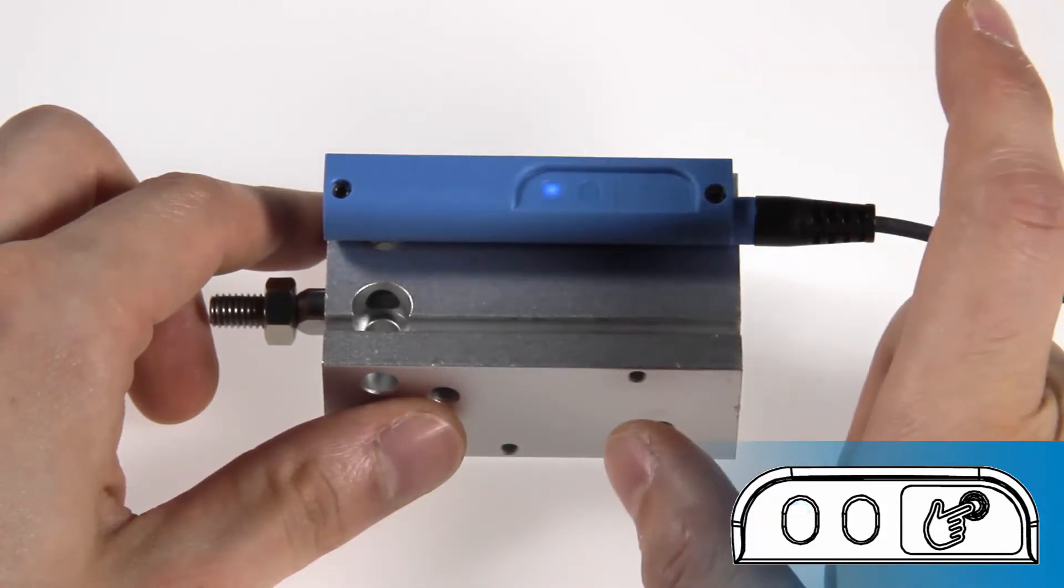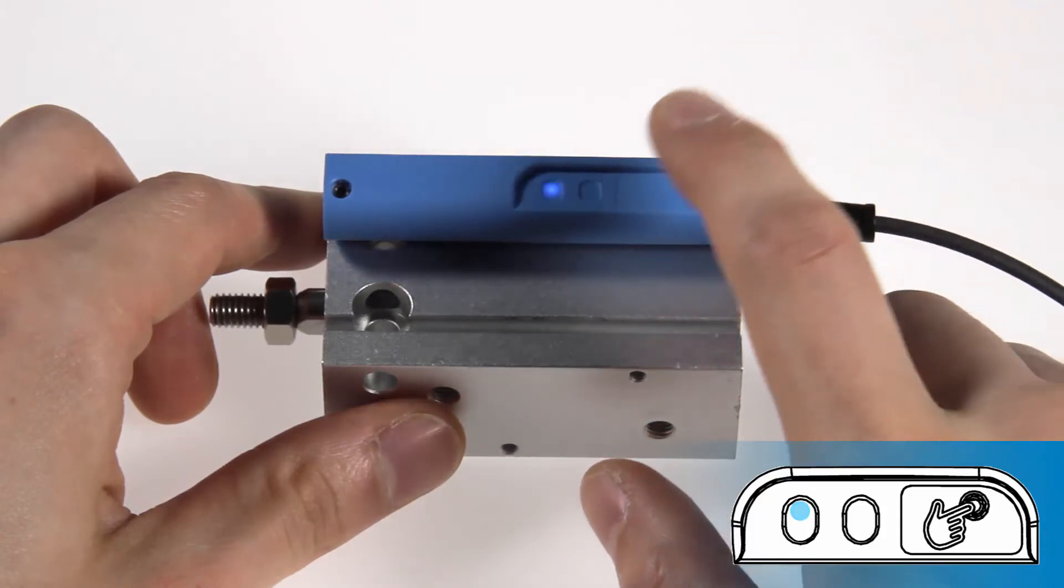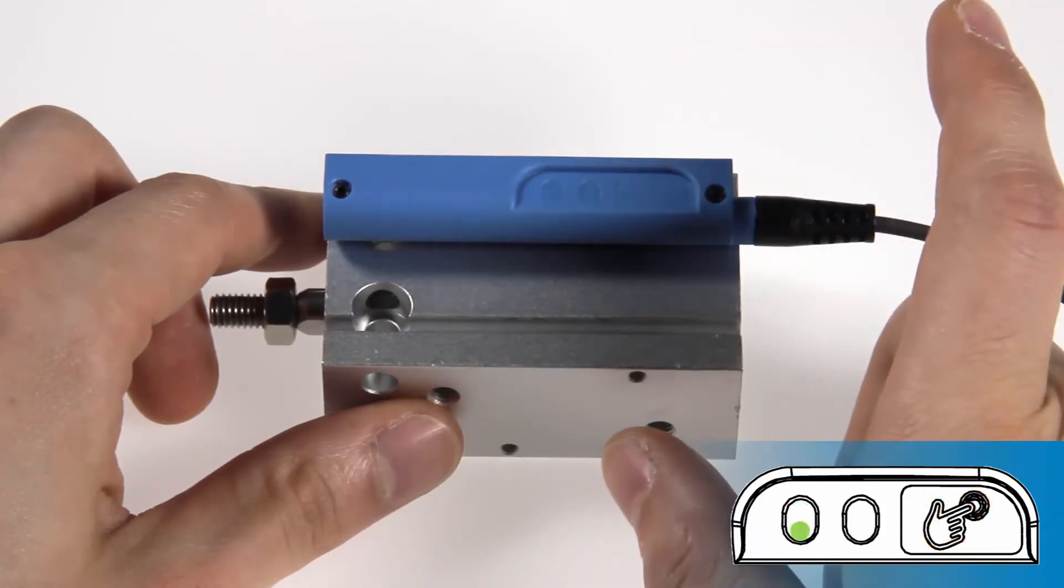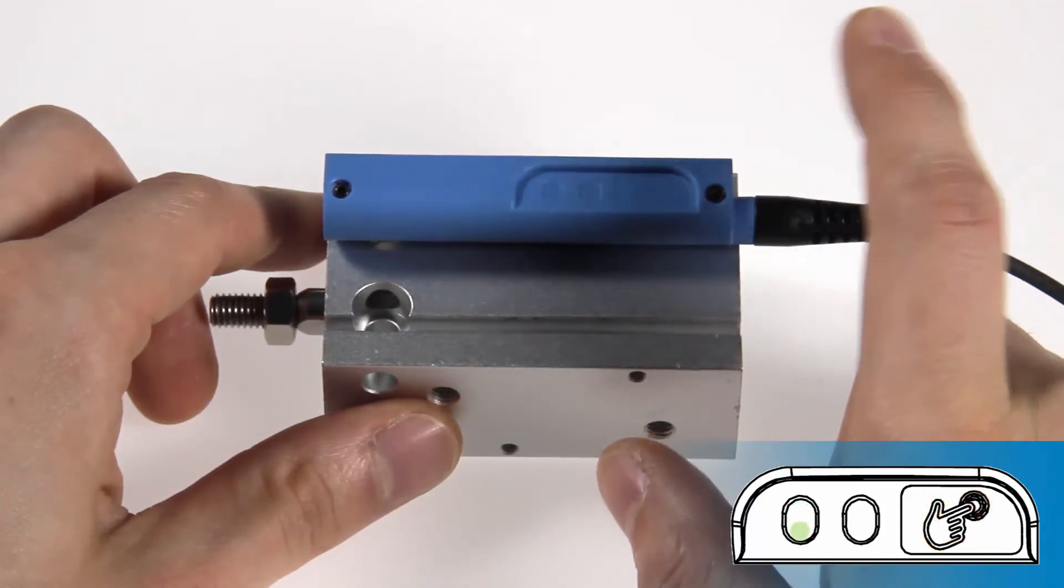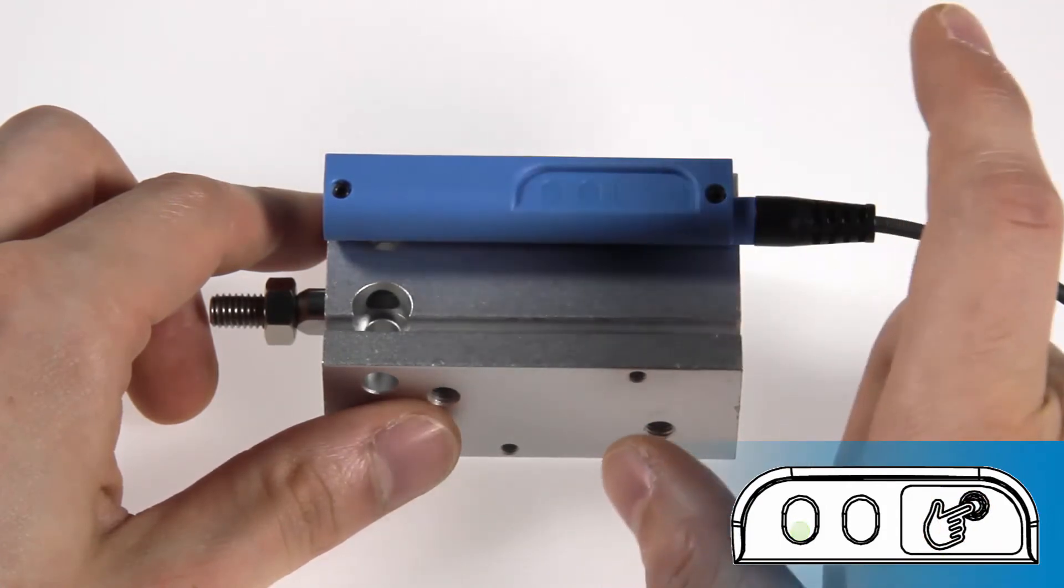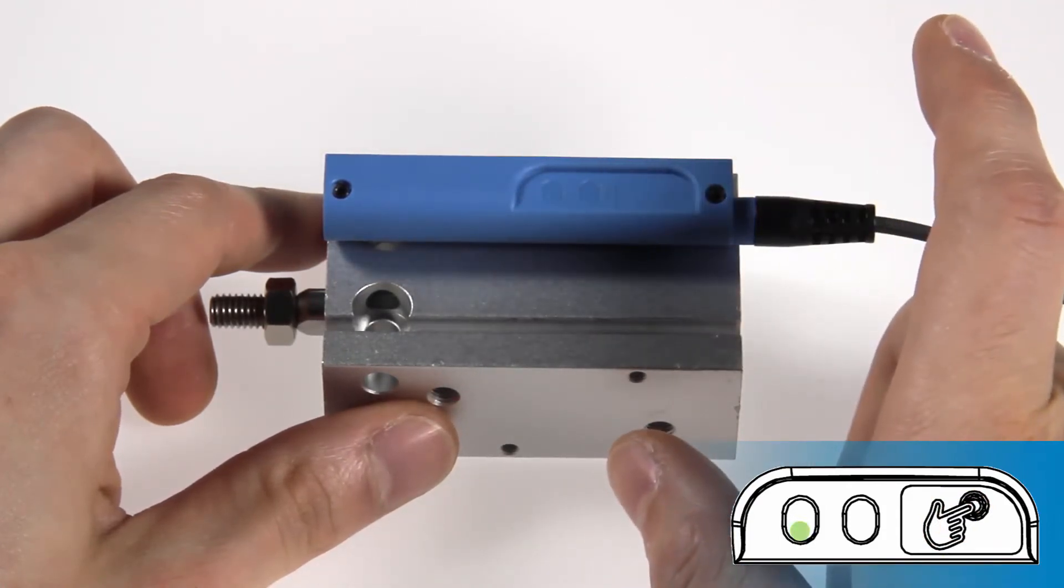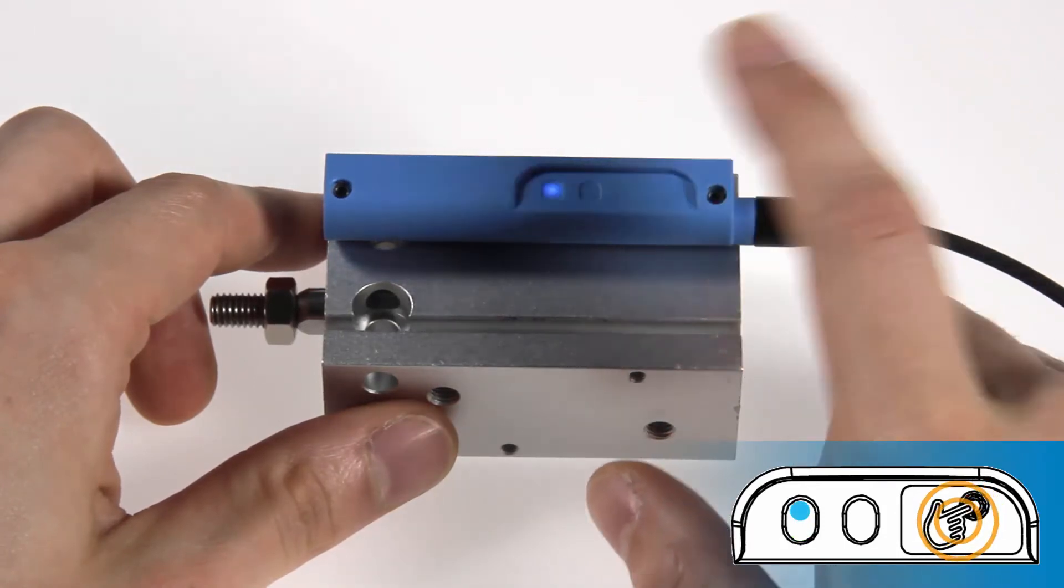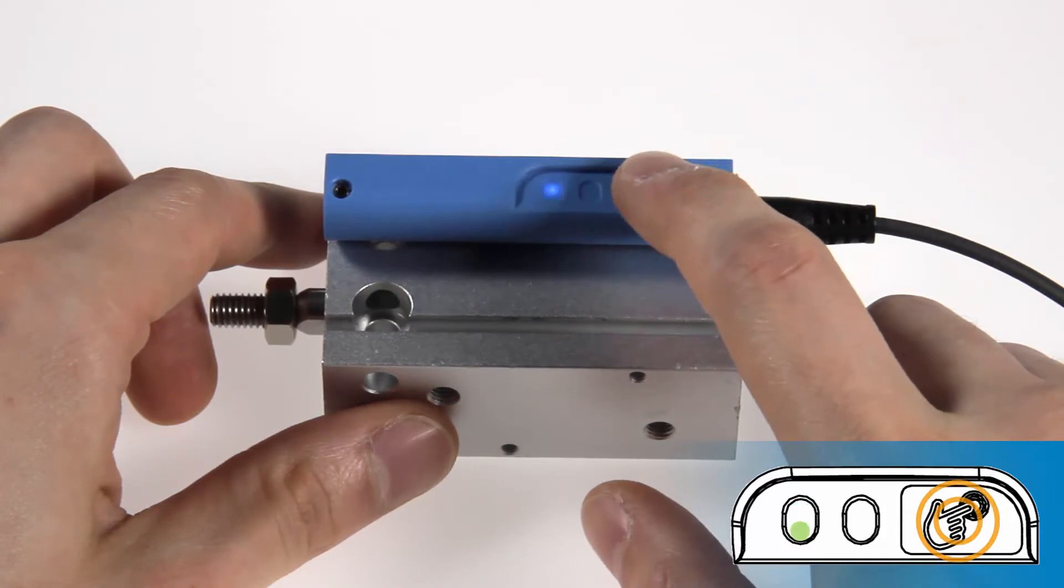In order to change the output to voltage, press the keypad again and the LED changes from blue to green. The green LED means that the voltage output is active now and the sensor provides a 0 to 10 volt signal in the set range. By pushing the keypad, one can switch between the current and the voltage output.